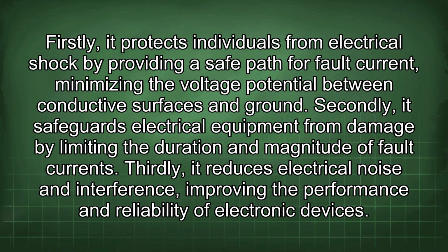Firstly, it protects individuals from electrical shock by providing a safe path for fault current, minimizing the voltage potential between conductive surfaces and ground. Secondly, it safeguards electrical equipment from damage by limiting the duration and magnitude of fault currents. Thirdly, it reduces electrical noise and interference, improving the performance and reliability of electronic devices.